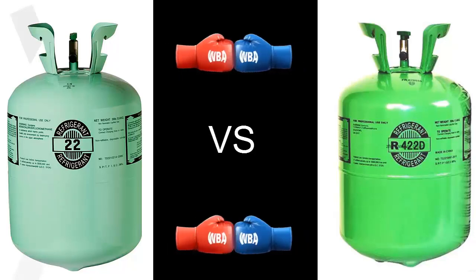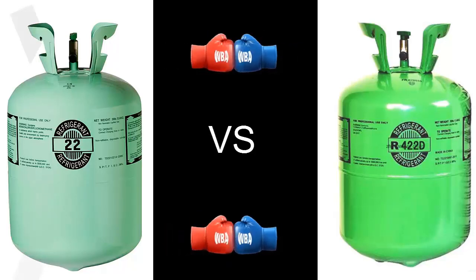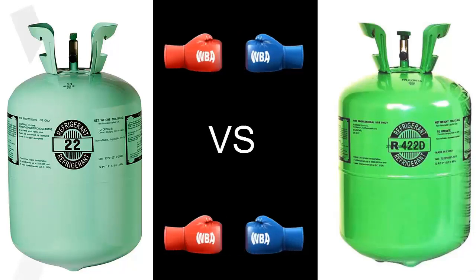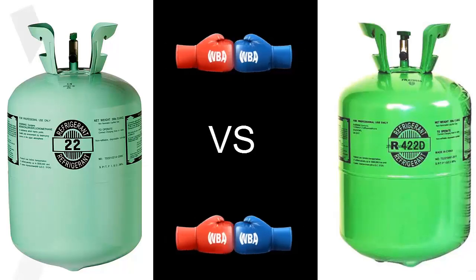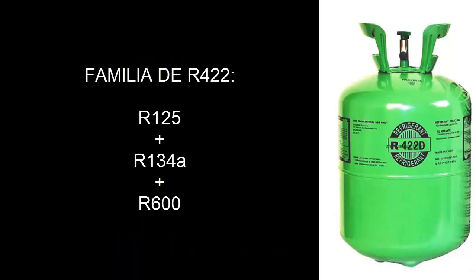R22 is a pure gas composed of a single component, while the refrigerants in the R422 family are formed by several components, such as refrigerant R125, refrigerant R134A, and isobutane gas R600.